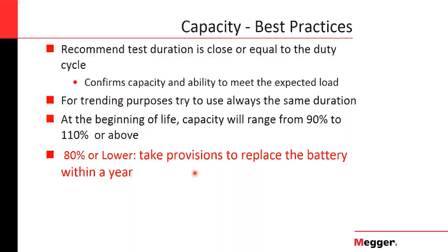And the criterion to replace the battery is when you reach 80% of the capacity. When that calculation comes out equal to 80% of capacity, that is the moment to replace the battery, and according to the standard, you have 1 year to do this.